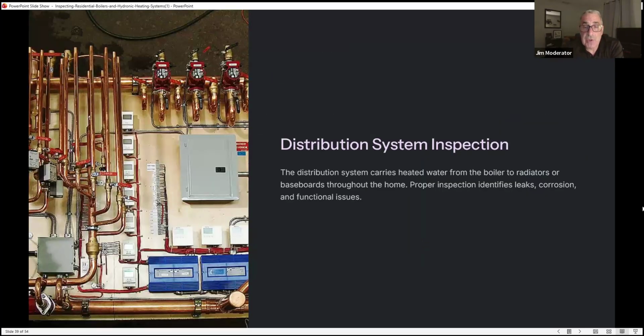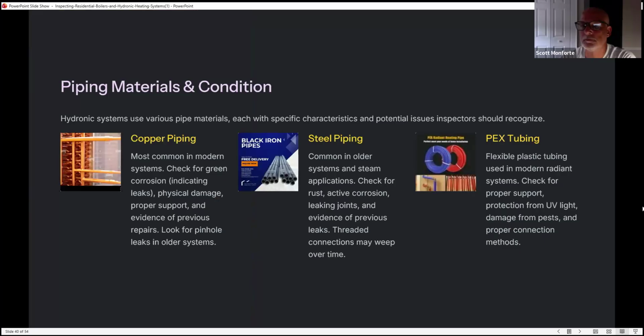Distribution system inspection. The distribution system carries heated water from the boiler to the radiators or baseboards throughout the home. Proper inspection identifies leaks, corrosion, and functional issues. Piping material and conditions: hydronic systems use various pipe materials, each with specific characteristics and potential issues inspectors should recognize. So copper piping, which is common in modern systems: you want to check for green corrosion indicating leaks, and physical damage. You want to look for proper support of the pipes and evidence of previous repairs. Look for pinhole leaks in older systems.